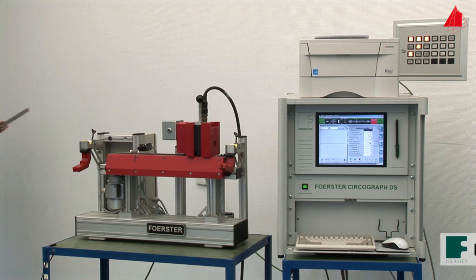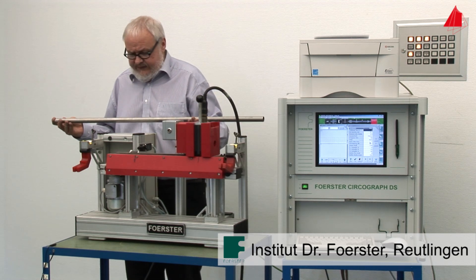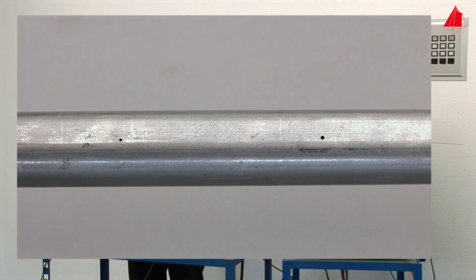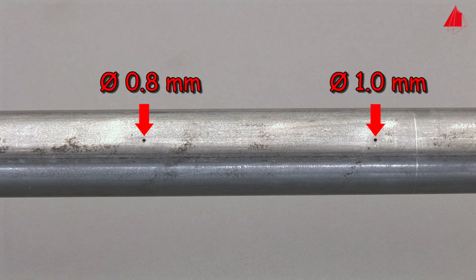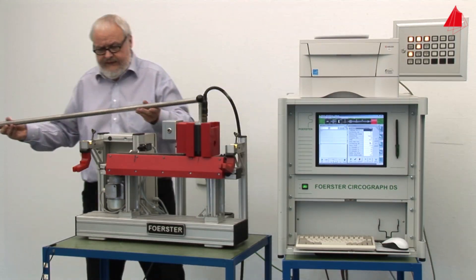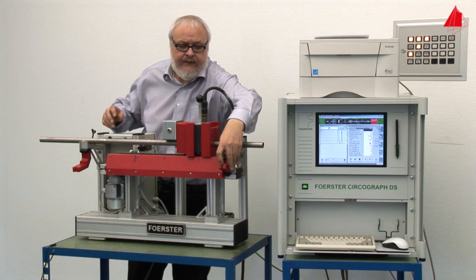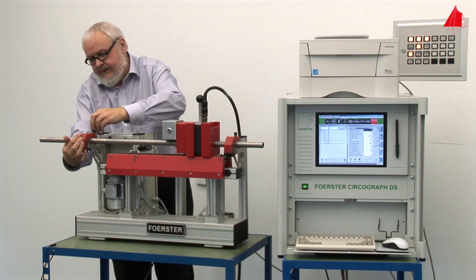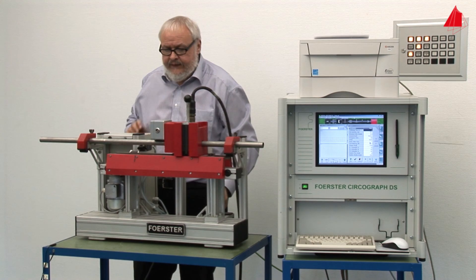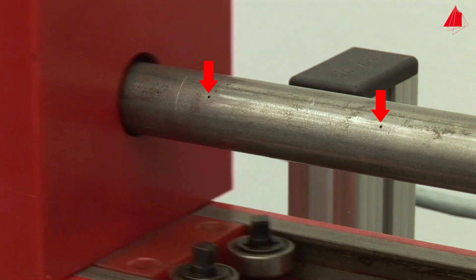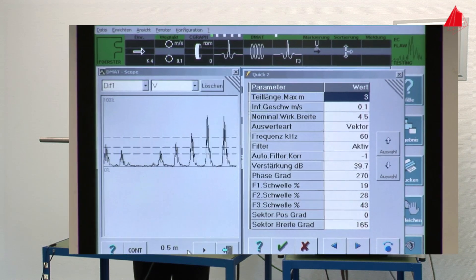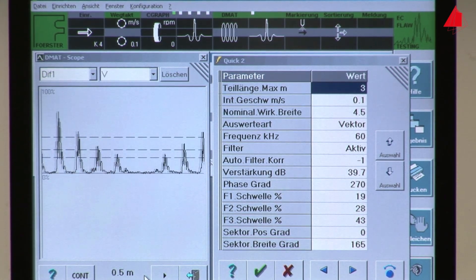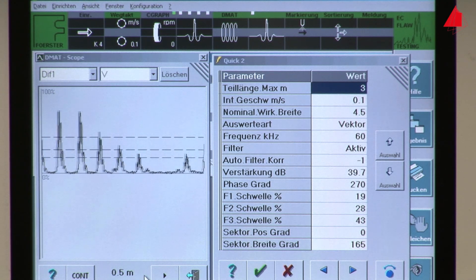If the coils are optimized even further, much smaller defects than our large saw cuts can be detected. This tube is made of a non-magnetic austenitic steel; four bore holes have been drilled through the tube wall, with diameters ranging from 1.4 mm down to 0.8 mm. Instead of performing the test by hand, a mechanized testing machine is used. By choosing appropriate test parameters and an optimized evaluation method, not only the locations of the holes along the axis can be determined — the diameter of the holes can also be approximately measured. However, with this coaxial probe it is not possible to determine the location of defects in the circumferential direction.